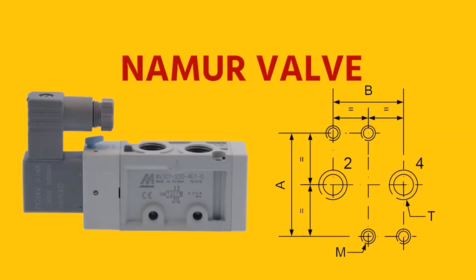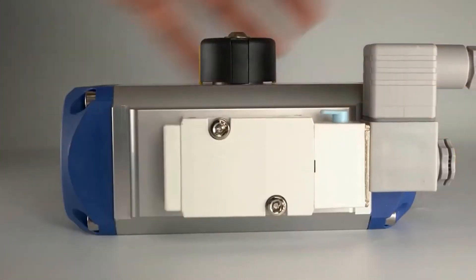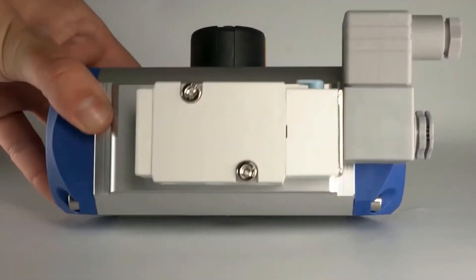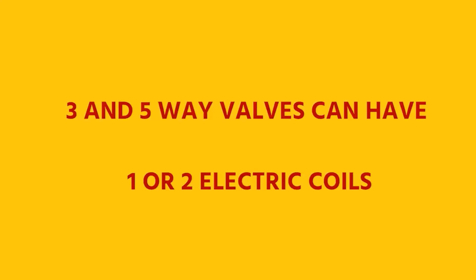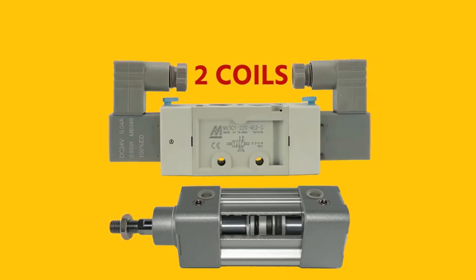Namur valves are a special type that have a standardized design to directly mount them to a valve actuator. They are easy to mount, compact and reduce the number of hoses and fittings. Three and five-way valves can have one or two electric coils. One coil means that the valve returns to a rest position with a power loss. Two coils means that it switches by providing a short pulse to one of the coils. With power loss, these valves remain in the latest position.